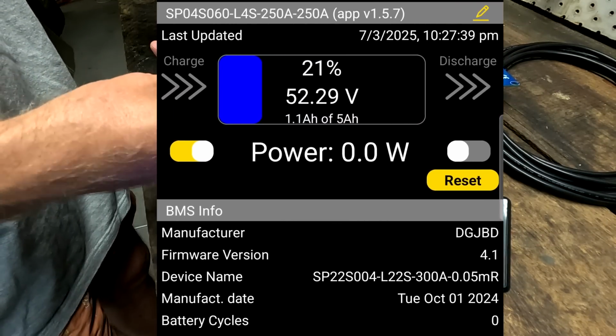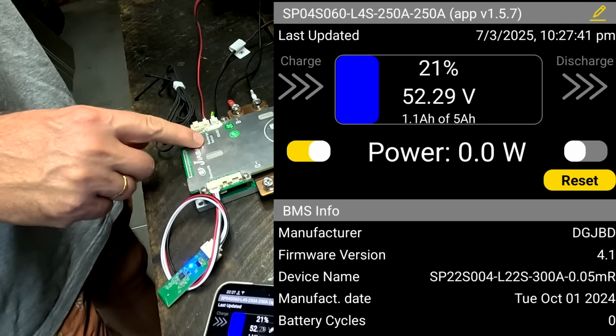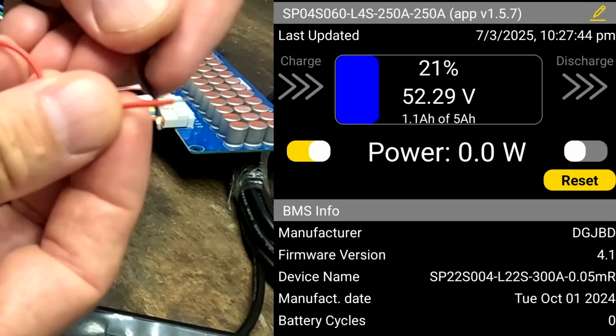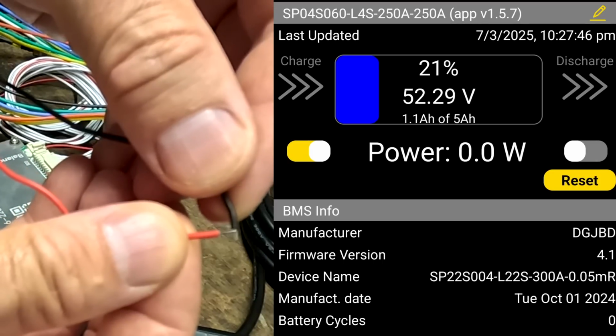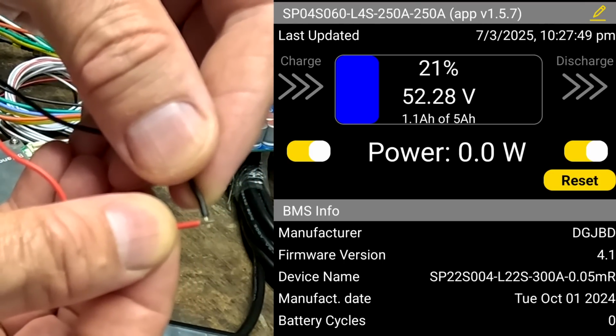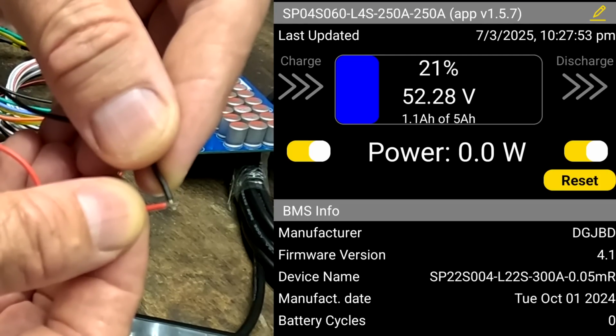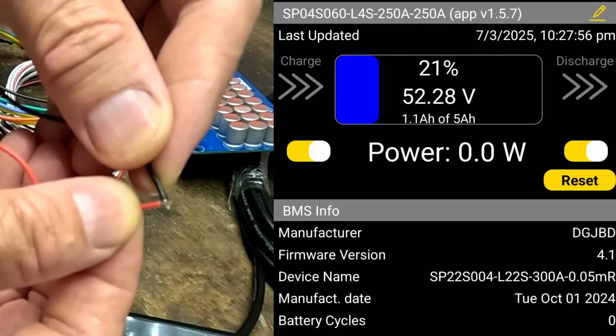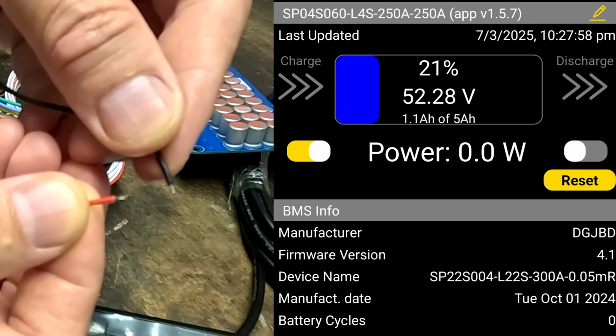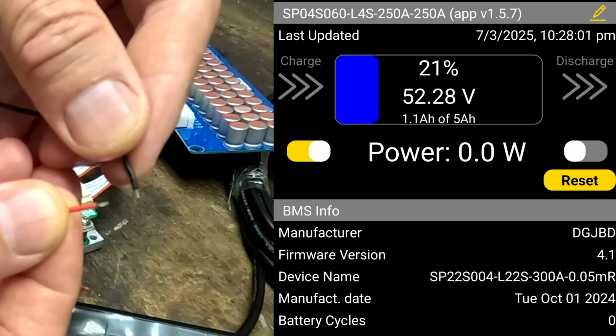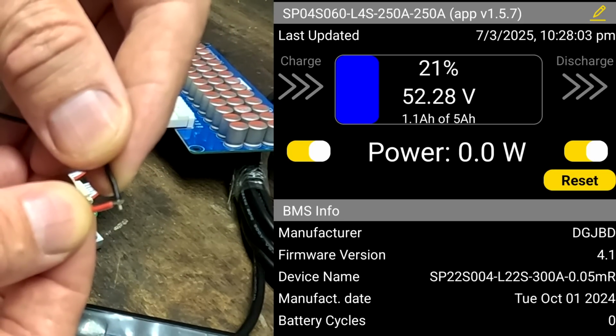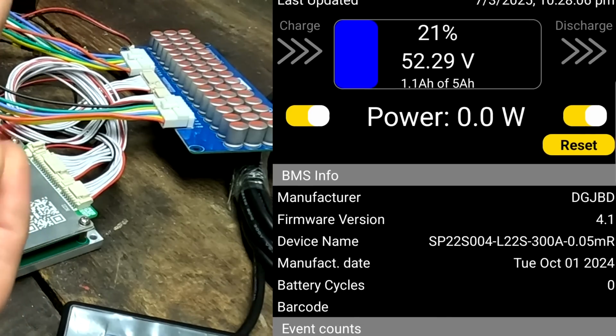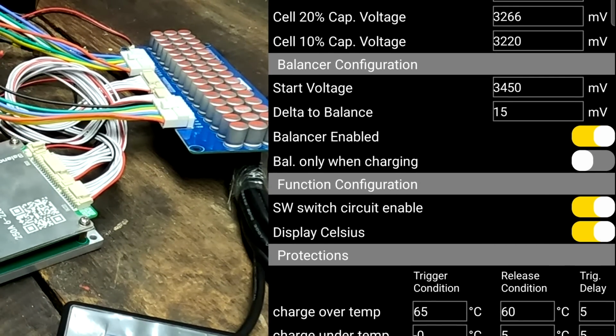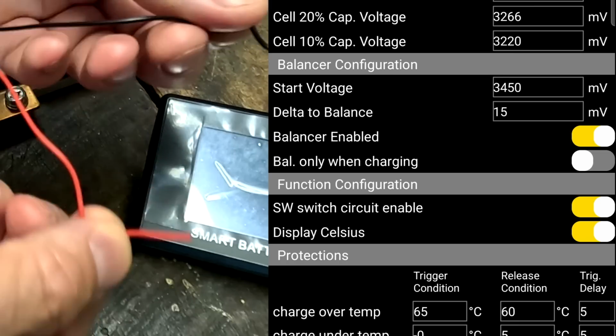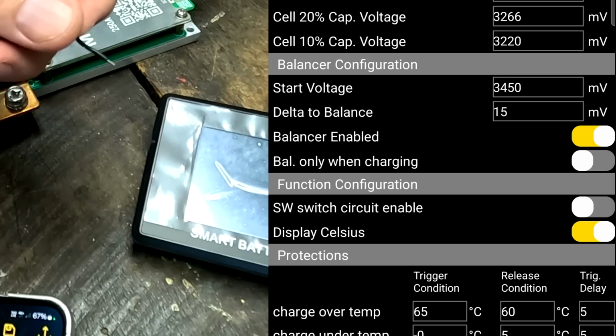If I take these 2 cables of the discharge switch, the bare ends, and hold them together to make good contact, we can see the discharge MOSFET in the BMS turns back on. If I disconnect the cables, the discharge MOSFET disconnects; connect them again, it turns back on. This switch here in settings enables this function.